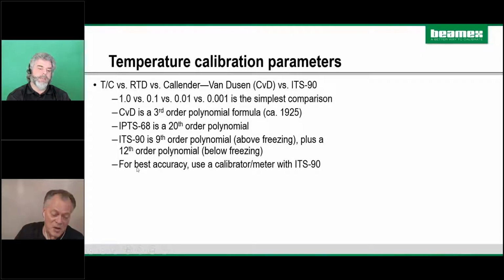So if somebody tells you they want to measure something super accurate, you need to get a calibrator or meter that can support the ITS-90 coefficient, and then you need to buy a probe. These probes start really around $500 and can go up to above $2,000 for these super accurate RTD probes with the coefficients. And you have to get them tested every year, and that costs extra.